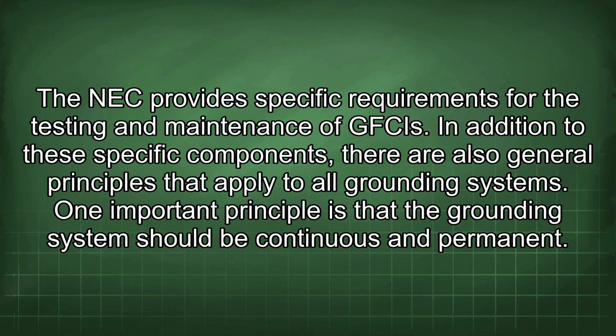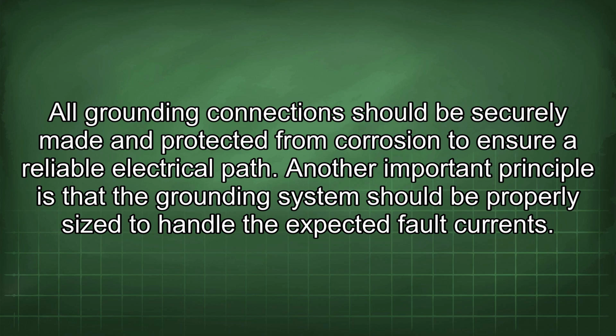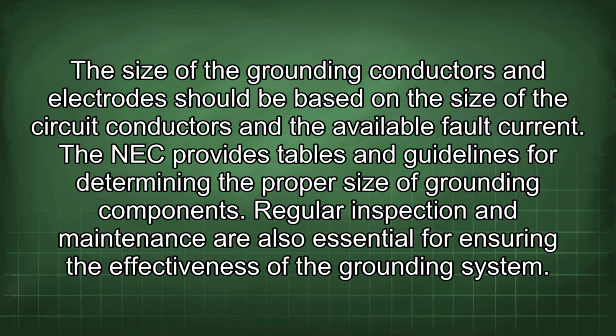In addition to these specific components, there are also general principles that apply to all grounding systems. One important principle is that the grounding system should be continuous and permanent. All grounding connections should be securely made and protected from corrosion to ensure a reliable electrical path. Another important principle is that the grounding system should be properly sized to handle the expected fault currents. The size of the grounding conductors and electrodes should be based on the size of the circuit conductors and the available fault current. The NEC provides tables and guidelines for determining the proper size of grounding components.